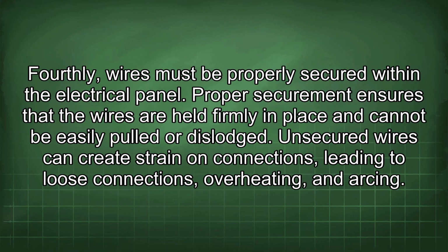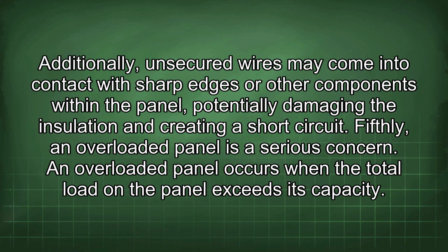Fourthly, wires must be properly secured within the electrical panel. Proper securement ensures that the wires are held firmly in place and cannot be easily pulled or dislodged. Unsecured wires can create strain on connections, leading to loose connections, overheating, and arcing. Additionally, unsecured wires may come into contact with sharp edges or other components within the panel, potentially damaging the insulation and creating a short circuit.